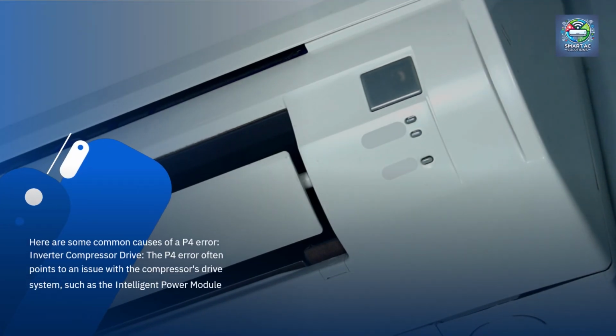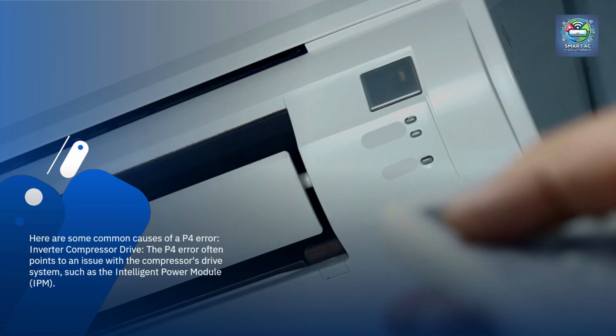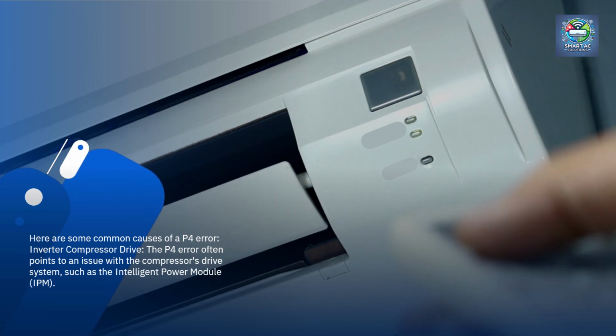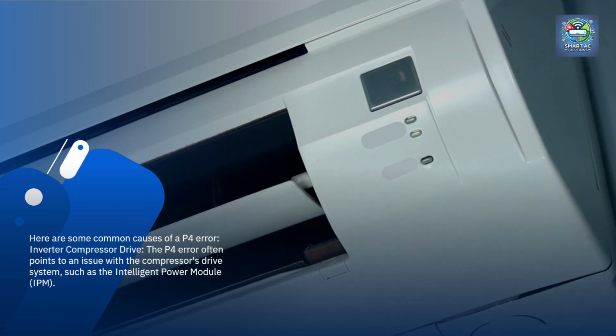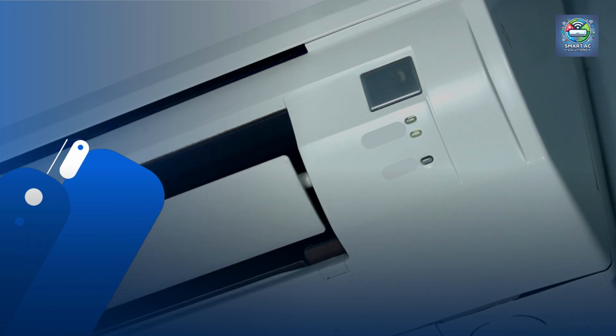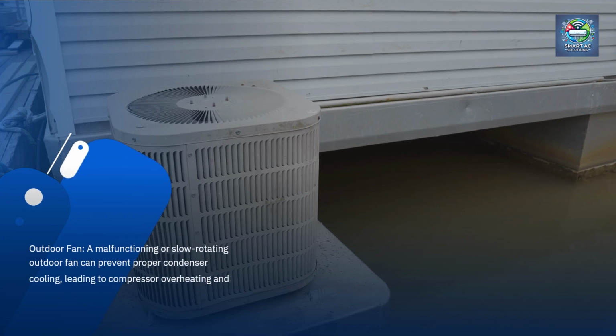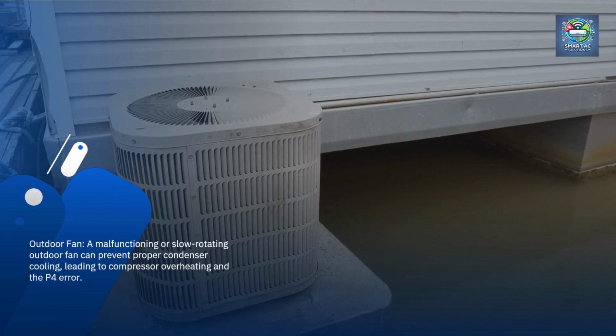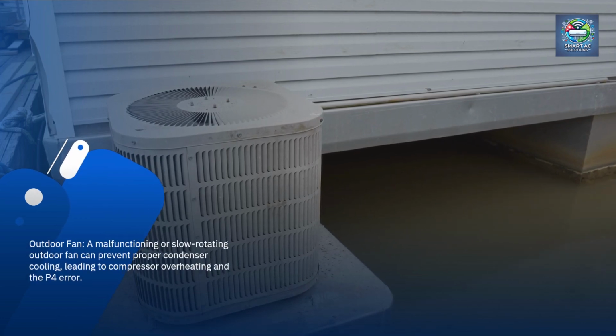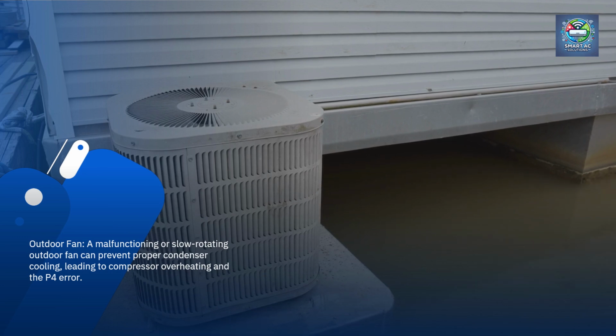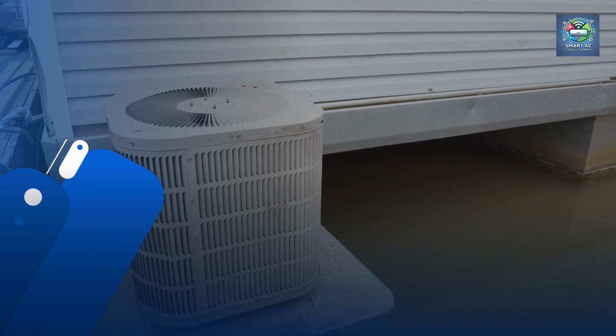Here are some common causes of a P4 error. Inverter compressor drive. The P4 error often points to an issue with the compressor's drive system, such as the Intelligent Power Module, IPM. Outdoor fan. A malfunctioning or slow-rotating outdoor fan can prevent proper condenser cooling, leading to compressor overheating and the P4 error.